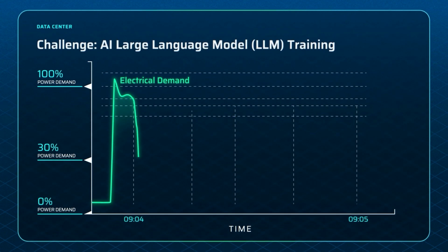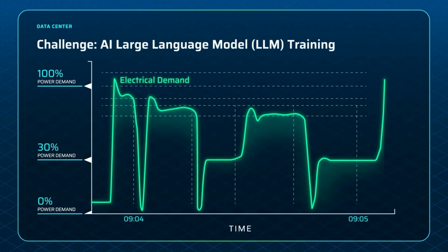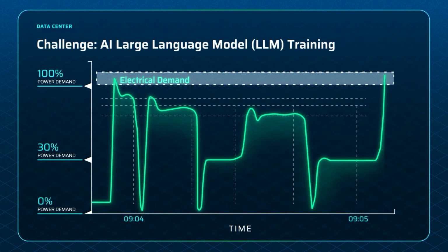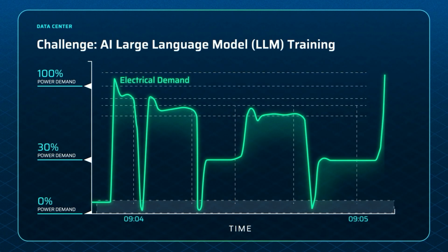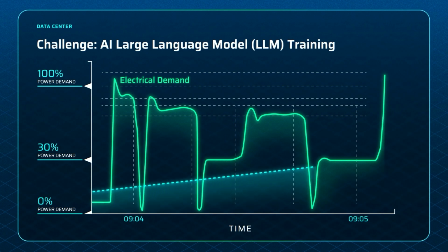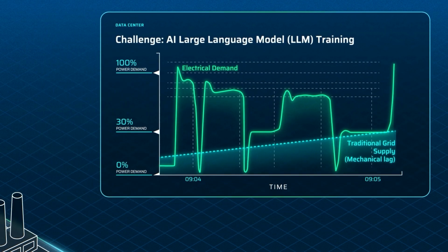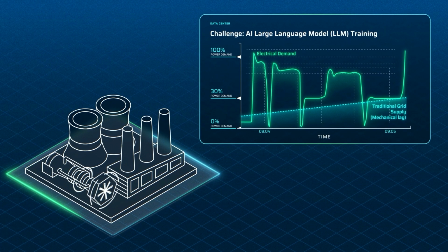The challenge is that AI training introduces massive step loads. These are power demands that spike from 0 to 100% and back again in milliseconds. These violent transients outpace the physical limits of traditional grid infrastructure. Conventional power plants rely on the mechanical inertia of massive spinning turbines, heavy equipment that simply cannot ramp up or down quickly enough to match these rapid swings in power demand. And this can lead to severe equipment damage and system instability.